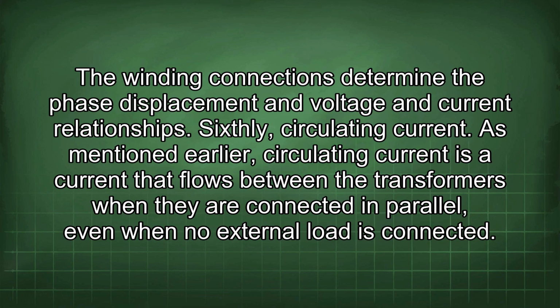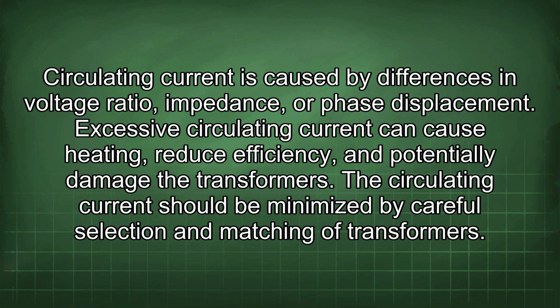Sixthly, circulating current. As mentioned earlier, circulating current is a current that flows between the transformers when they are connected in parallel, even when no external load is connected. Circulating current is caused by differences in voltage ratio, impedance, or phase displacement. Excessive circulating current can cause heating, reduce efficiency, and potentially damage the transformers. The circulating current should be minimized by careful selection and matching of transformers.